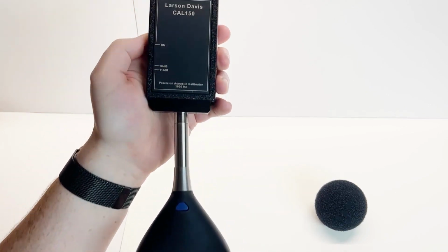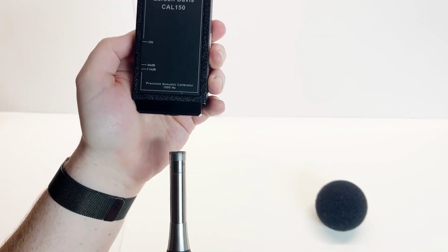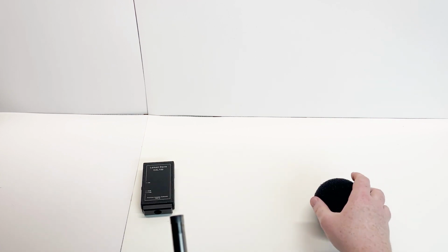Now gently remove the microphone from the opening at the bottom of the calibrator. When doing this, avoid twisting the microphone, pull straight out. The instrument is now ready to be used and calibrated.